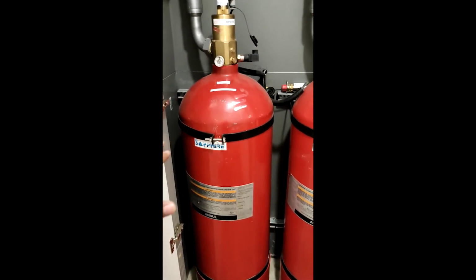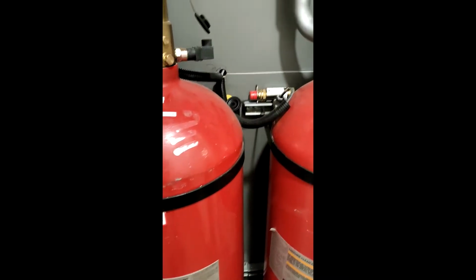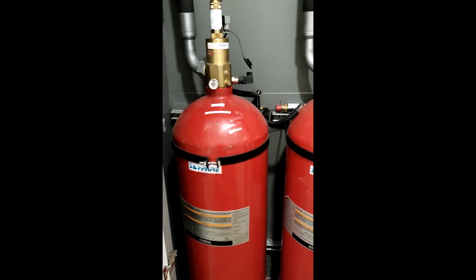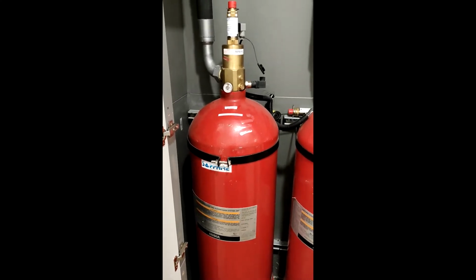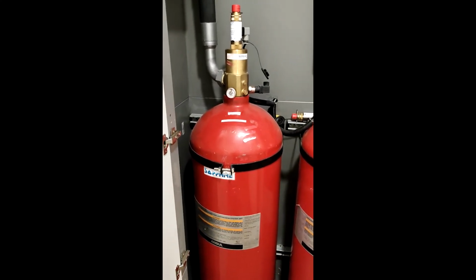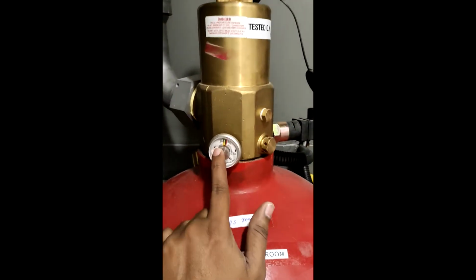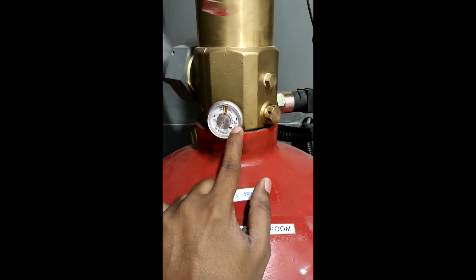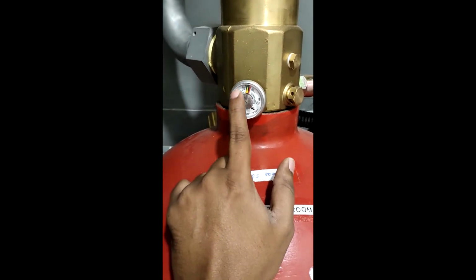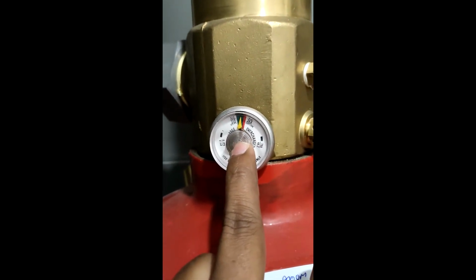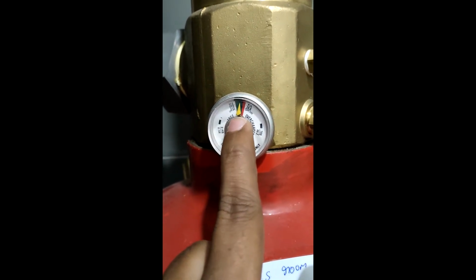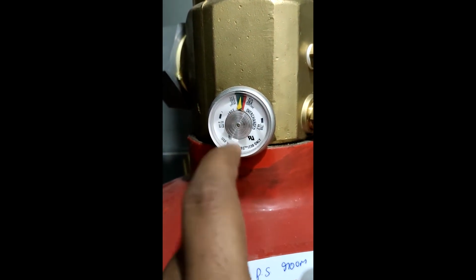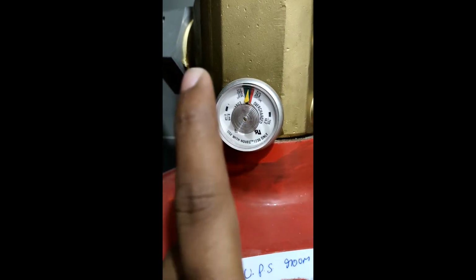Okay, so these are the Novec cylinders, with a total weight of 240 kg, and 80 kg of Novec 1230 gas is fed inside the cylinder. This gas is calculated as per the room size. Here we can see the pressure gauge, which shows how much pressure is inside the cylinder. See, it's in green color. This pressure gauge shows the current pressure of the cylinder.